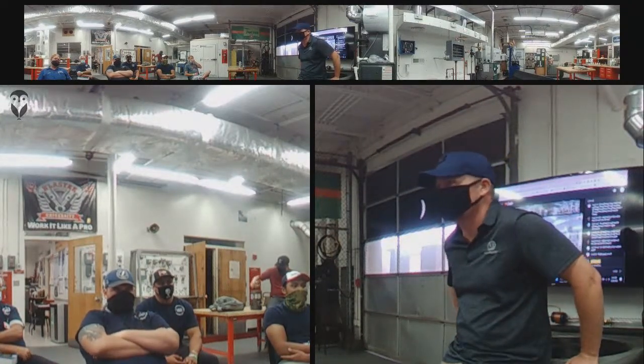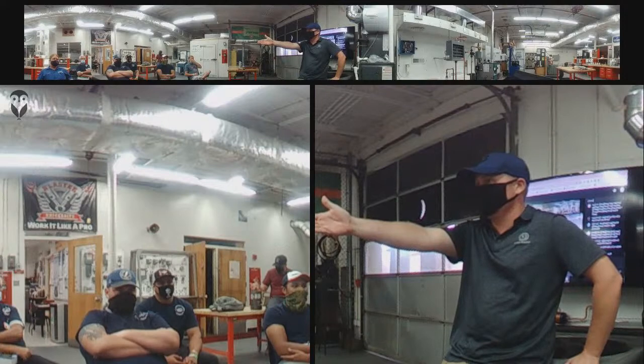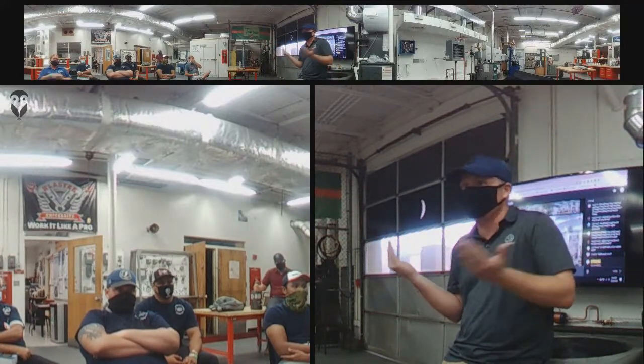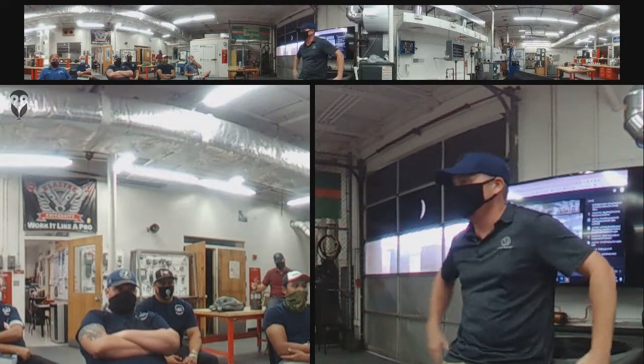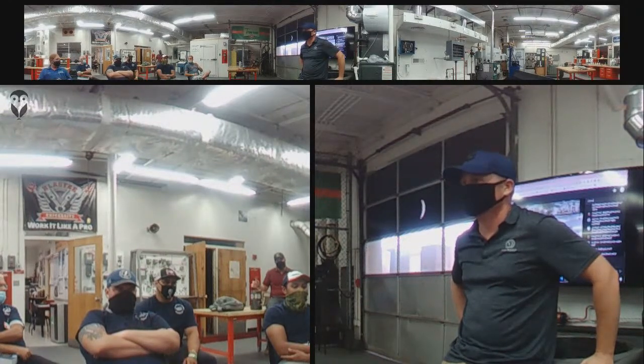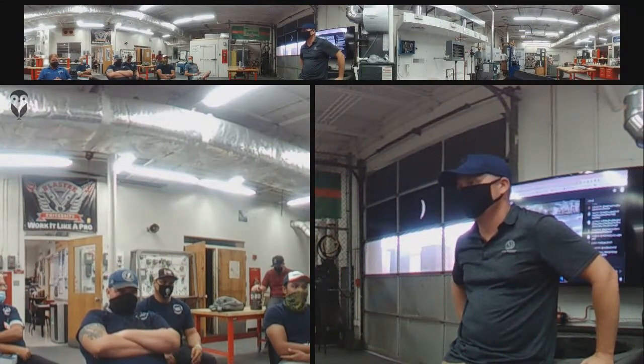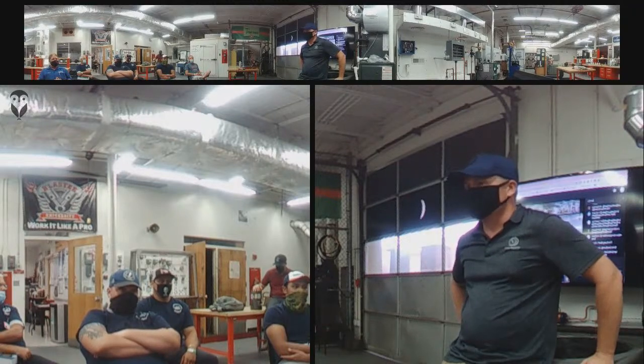And if you don't have a call on G, then look for exactly what you're saying. Maybe they hooked up the wrong G wire. Maybe they hooked up the one going to the condenser rather than the one going to the thermostat. Yeah, because they have the Y and the G wire, and they just mixed it up. Yeah, that's a good one.